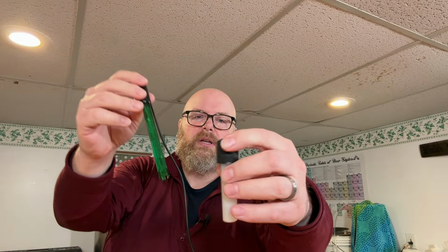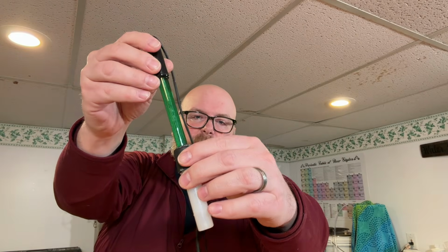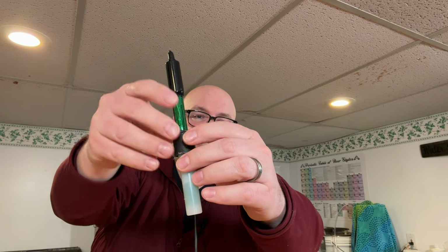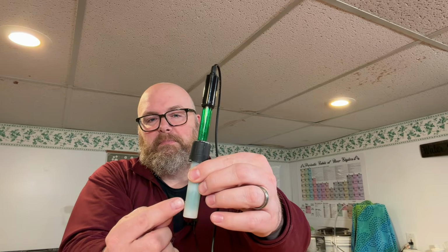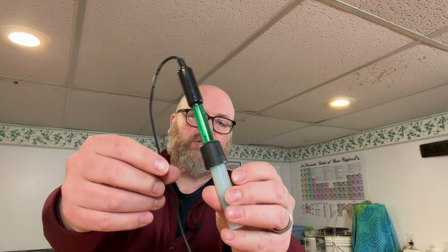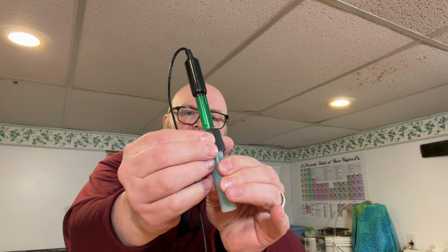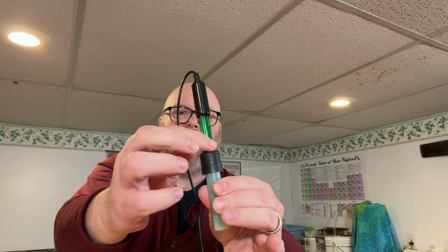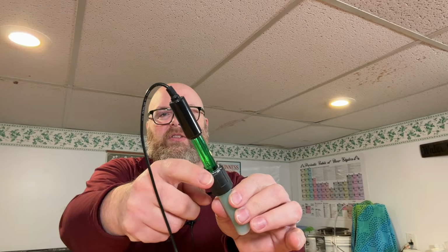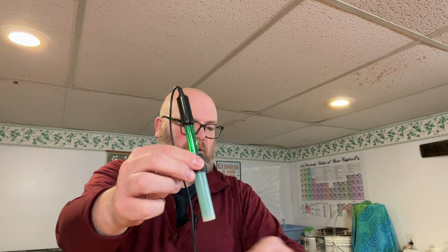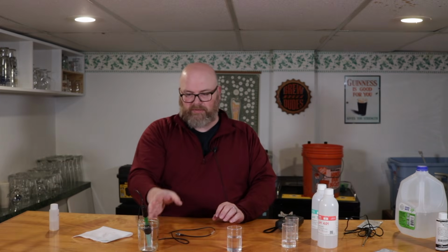So all you have to do is then slip this probe right back into the tube, and you'll see the solution come up the sides of the tube, but you just want to ensure that the base of the probe is submerged in that storage solution. And then you just tighten this down a little bit, and it'll make somewhat of a seal there. It's not a great seal. You can see all the salt on there. So anyway, that's all tightened up like that, and so that's ready to go, just to sit at room temperature until you're ready to use it next time. So I'm going to put that back in my jar so it doesn't flip over.